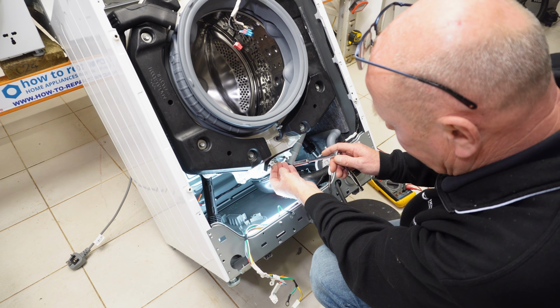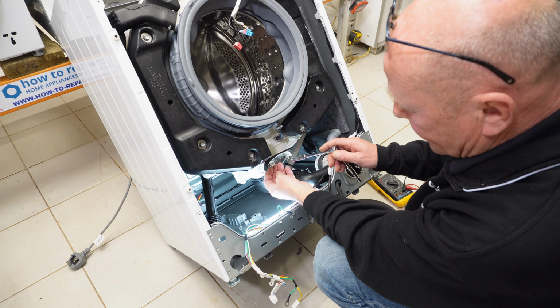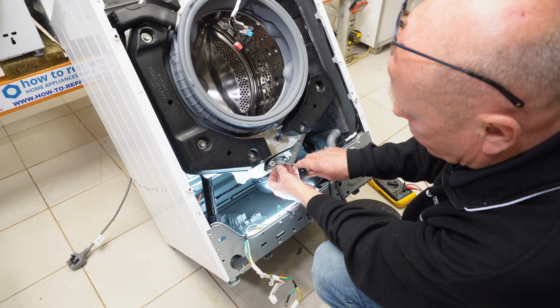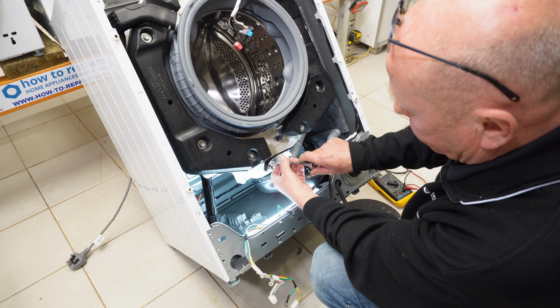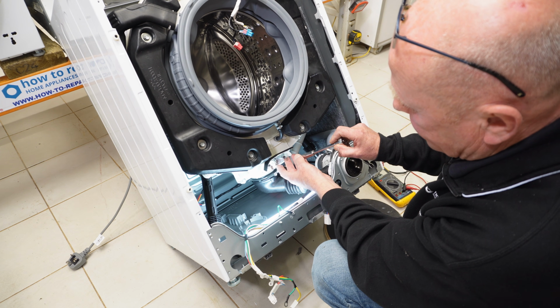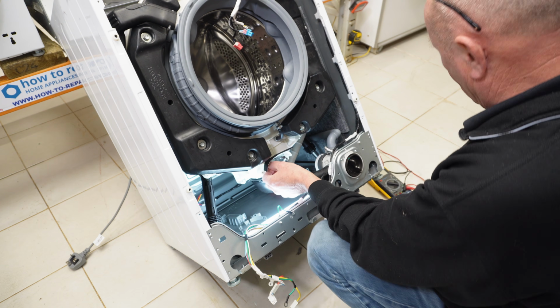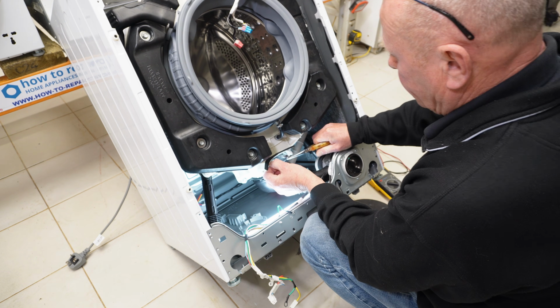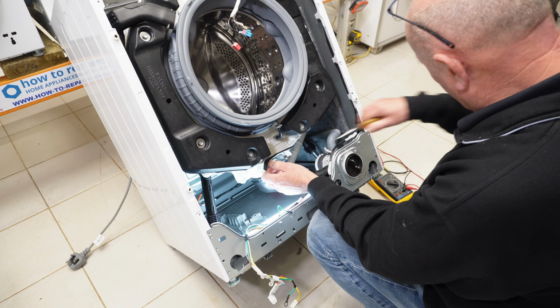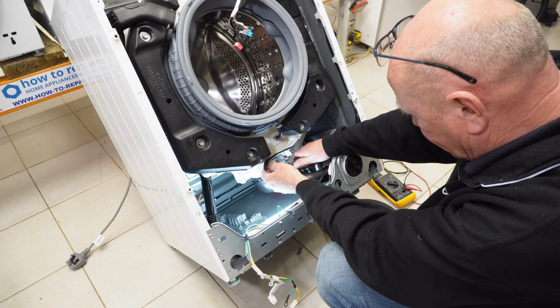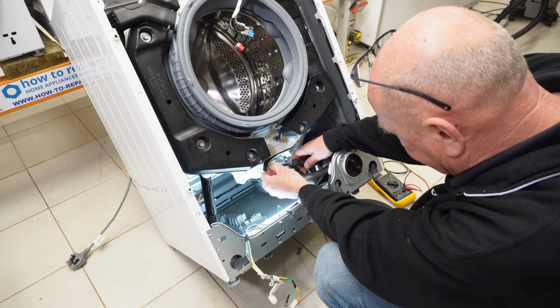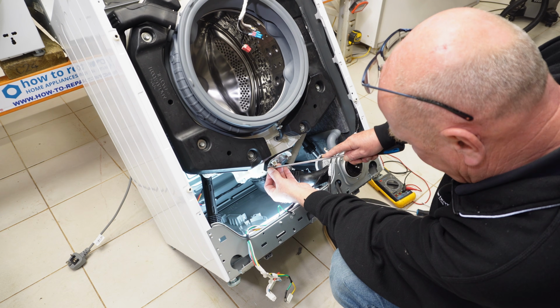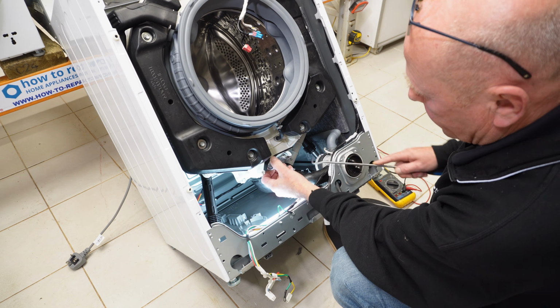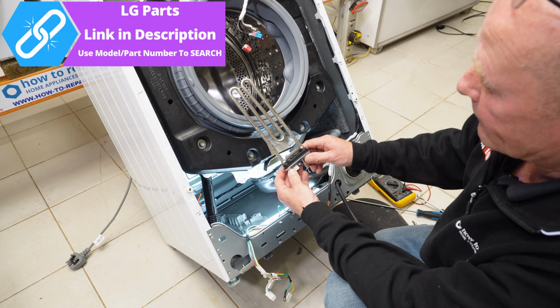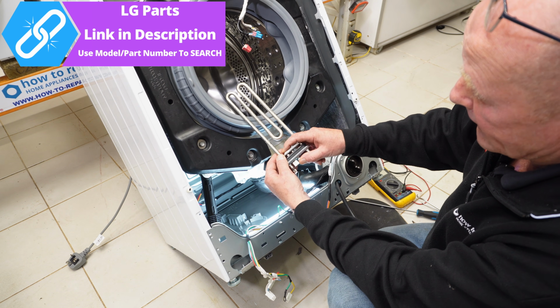To remove the heating element and the NTC sensor, it is possible to prise the NTC sensor out, but you want to release the pressure off this bolt first. Now, what I always do is back this up all the way to the end of the thread, then give it a push inwards. The element will come away, but sometimes they are hard to get out, and you will have to take your time and prise the element out. Sometimes the seal can be sticky and difficult to get out, so it's worth having a hook to actually pull the element out. And here we have the element and the NTC sensor. Again, these are sometimes sold as a complete unit.